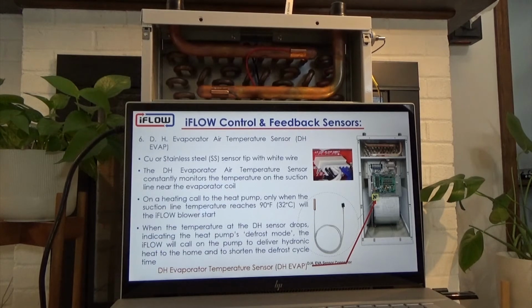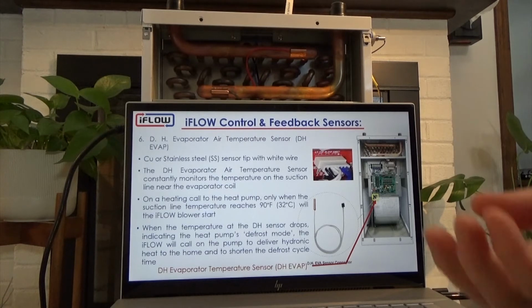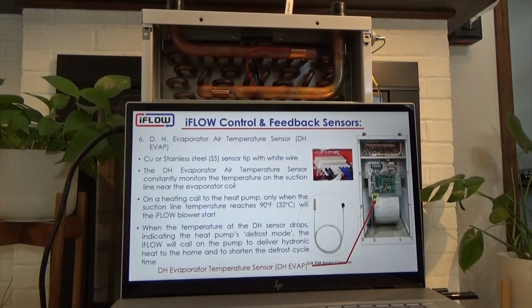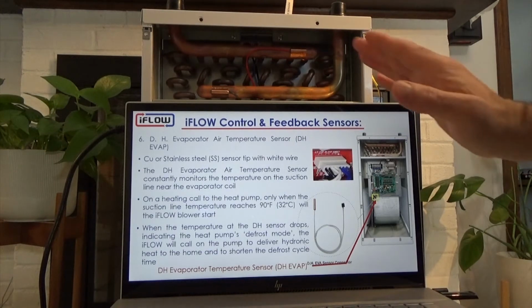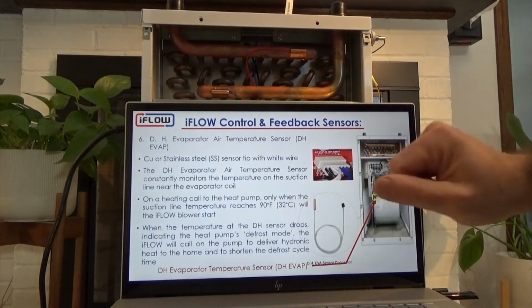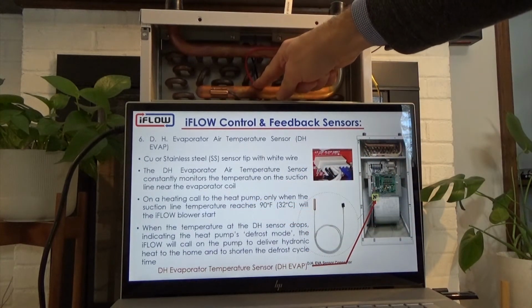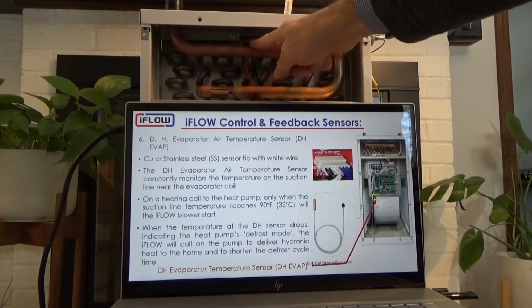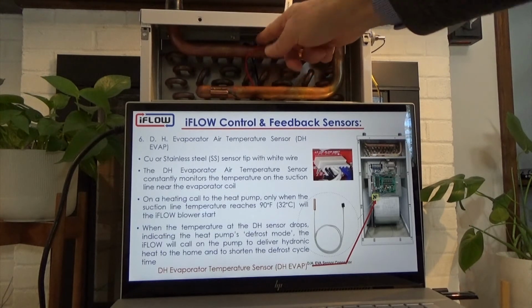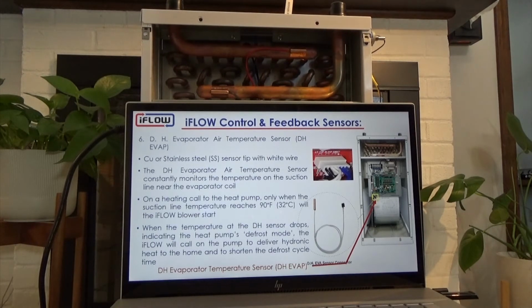When you get a call for heat and we're using a heat pump, we're going to look at the suction line temperature. When it reaches 90 degrees, then we know that we're supplying sufficient heat to the evaporator coil, and then we will bring on the blower to deliver heat into the home. If the temperature on the suction line does not reach 90 degrees, just the same as if the temperature coming into the hydronic coil doesn't reach that temperature, we're not going to start the blower because we don't want to be delivering cold air into the house.